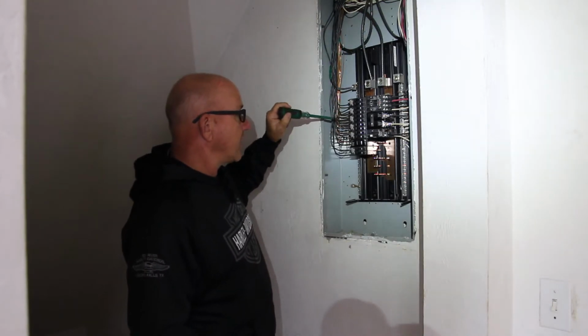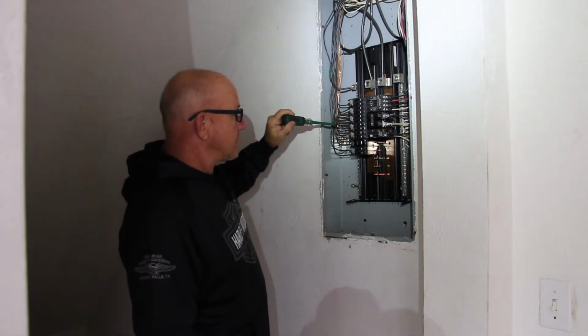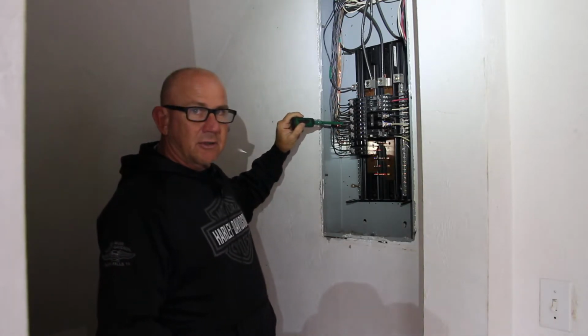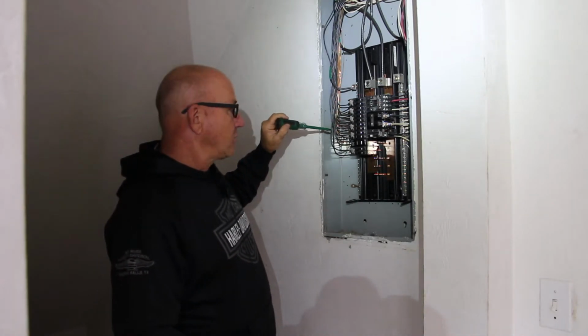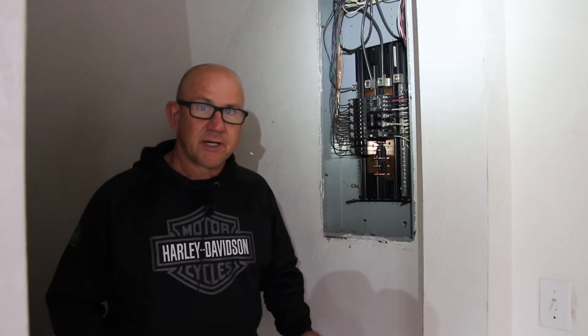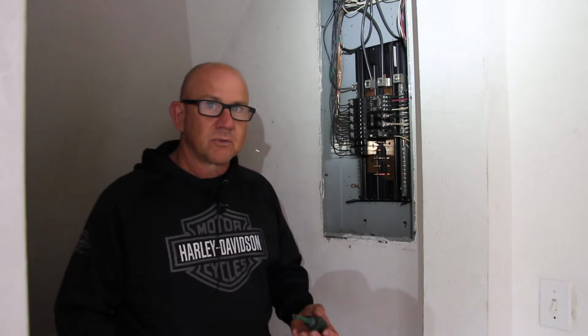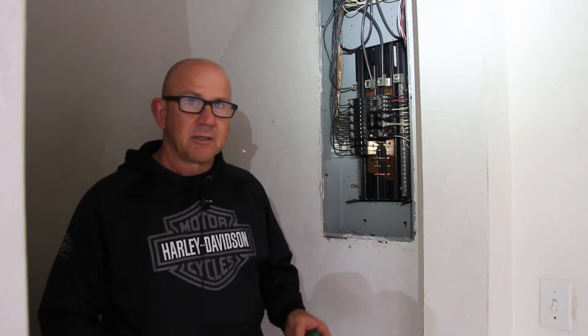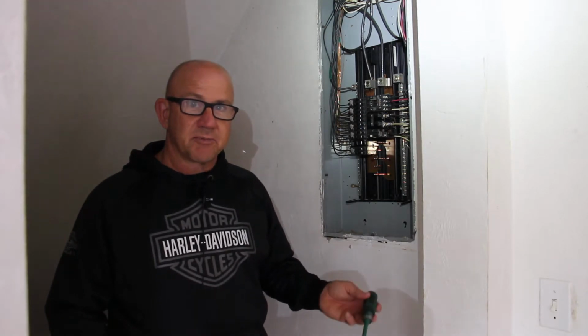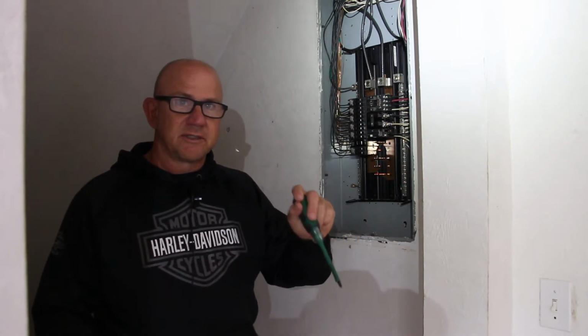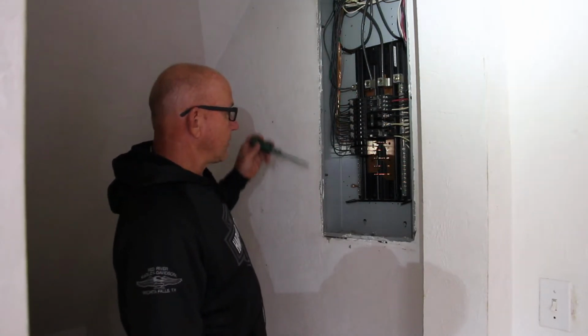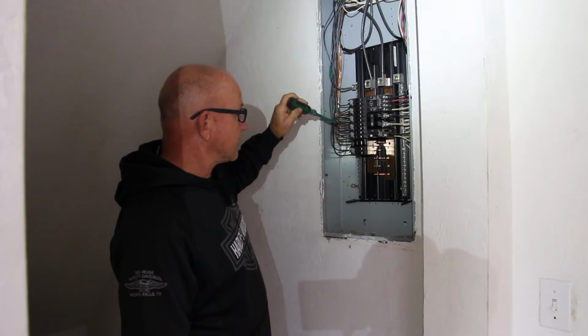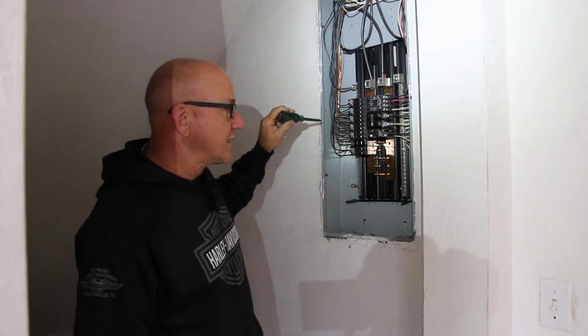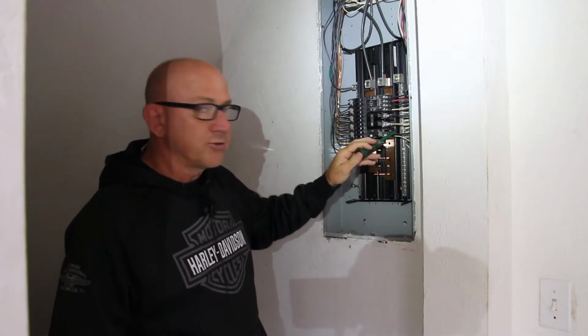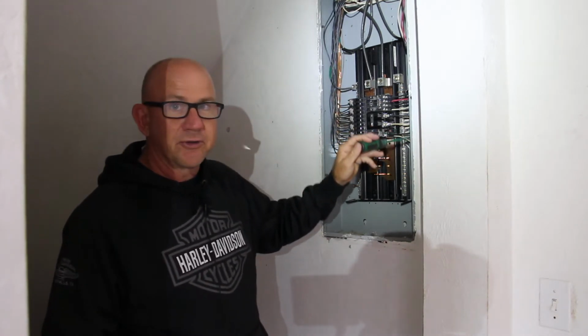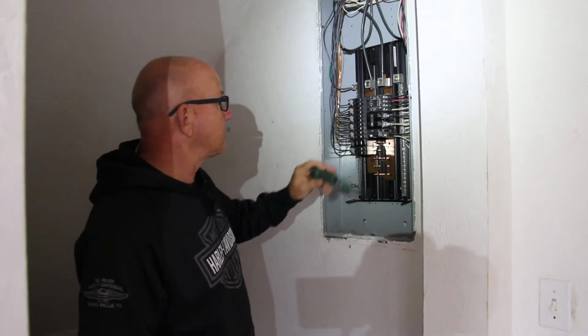Over here on our grounding bar, we have double taps on our grounding bus bar, which is approved by the panel manufacturer. However, part of that approval requires that the wire sizing is the same. You can't have a 12 and a 14 wire on the same terminal because there are different variations of thicknesses. We have a couple of problems here where there are at least 3 terminals that have 2 different wire sizes on them. Over here on our neutral bar, we have double taps on the neutral terminals. Those should all be on a single terminal.